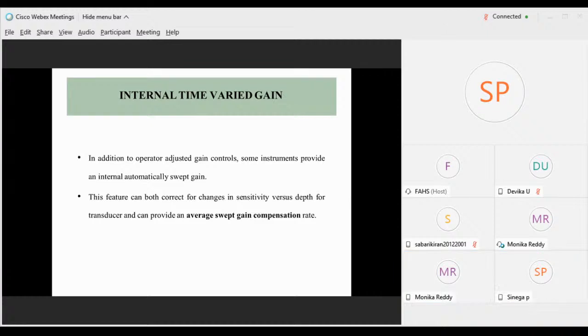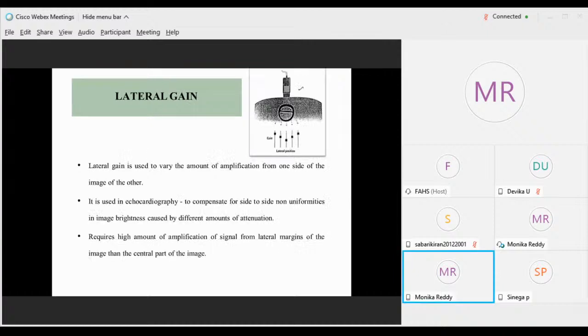Other than the gain controls, there is the internal time varied control, which gives the average swept gain compensation rate based on sensitivity versus depth. Lateral gain is used to vary the amount of amplification from one side of the image, not the center. It concentrates on the lateral sides and is mostly used in echocardiography. To compensate for side-to-side non-uniformities in image brightness, lateral gain is useful to increase the brightness on the sides.